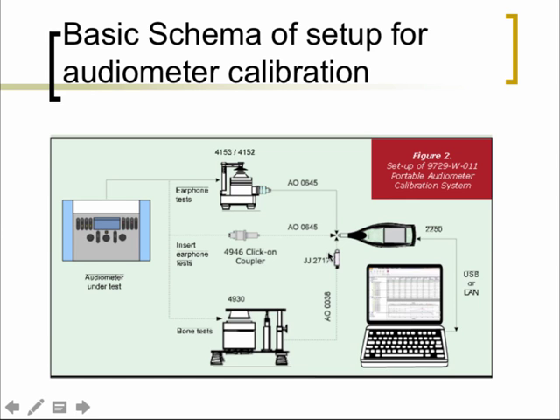Here is a schematic illustration of the setup used with audiometric calibration. The sound level meter may be connected to a computer — most recent digital ones are. You can readily see the output of the sound level meter in a table and input findings into software. When GSI calibrates the audiometers in our clinics, it's set up connected directly to a computer. The sound level meter has a microphone at the end, and different couplers are used depending on the transducer.